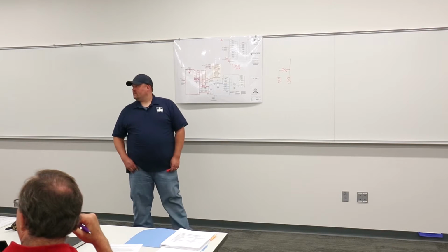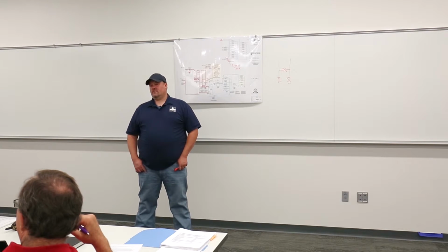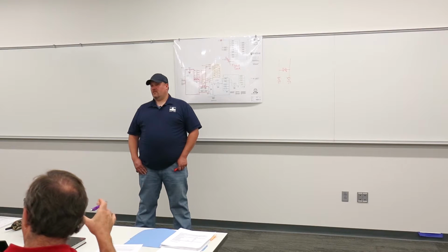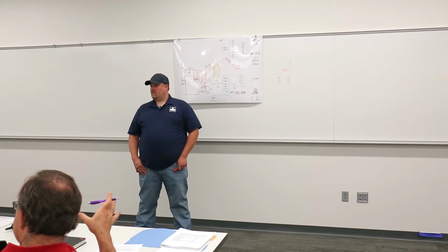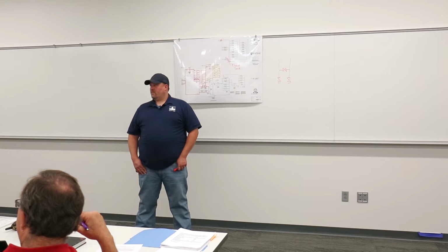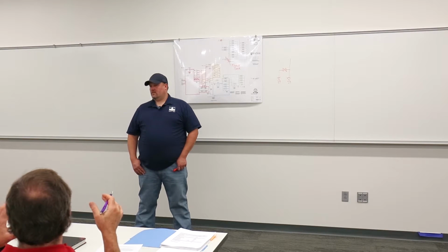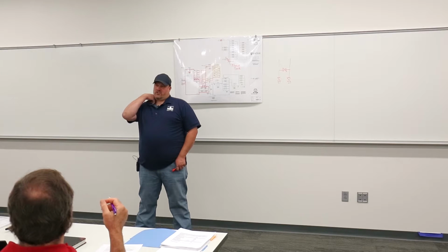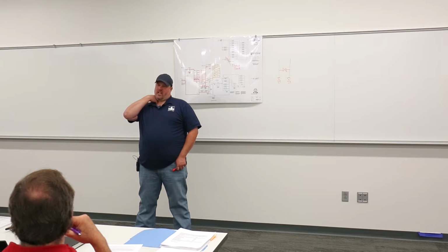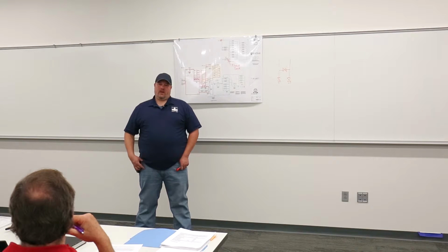So, Jamie, you say that you never shut the supply off from the campus on the chilled water, you shut the return off? The return's the only one with a control valve. So would the supply from the campus theoretically be makeup? Yes. Oh, okay. Yeah, it's makeup and it sets the pressure for the chilled water. It's the same as if it were operating. Like ours, I think our water makeups are set at like 30 PSI, 30, 32, something like that. And the system pressure coming in is like 60 something.